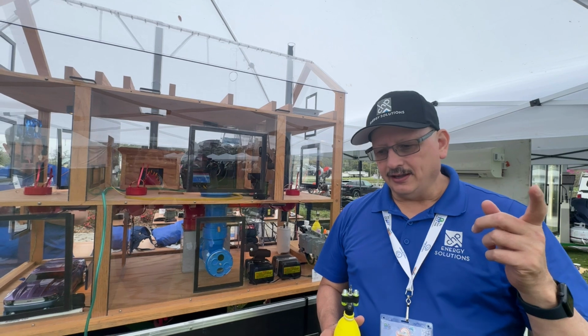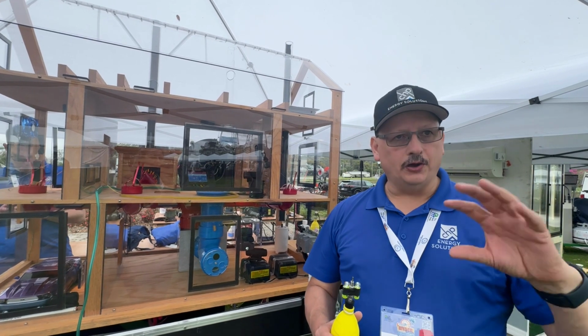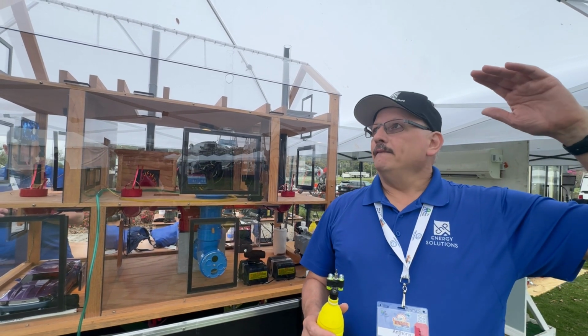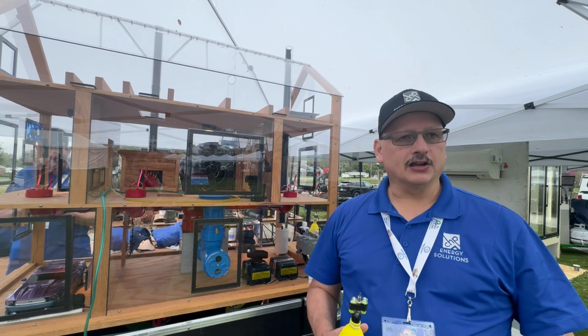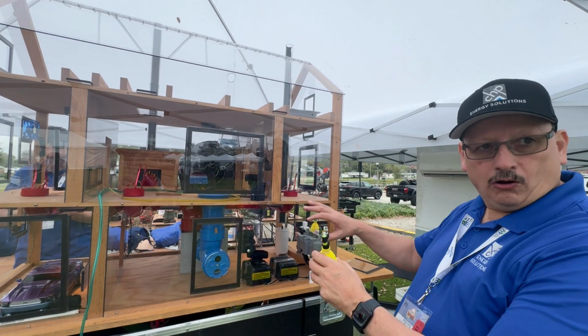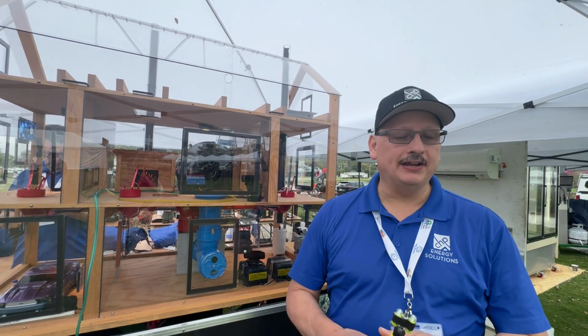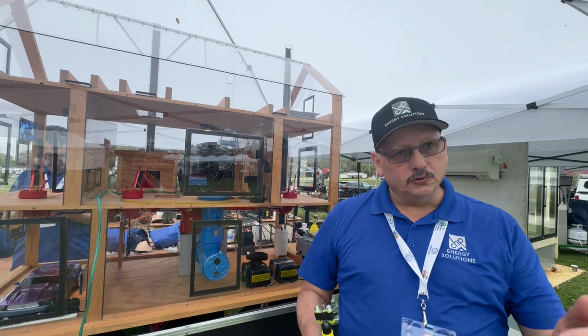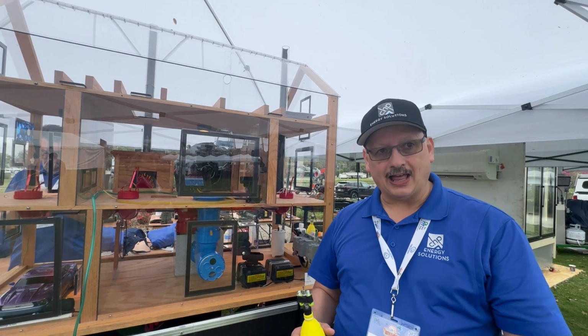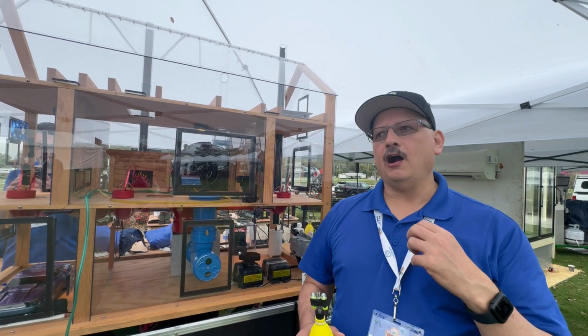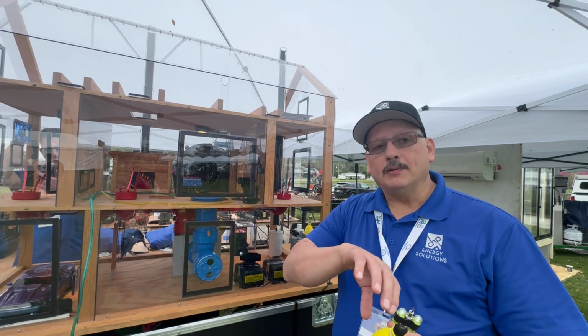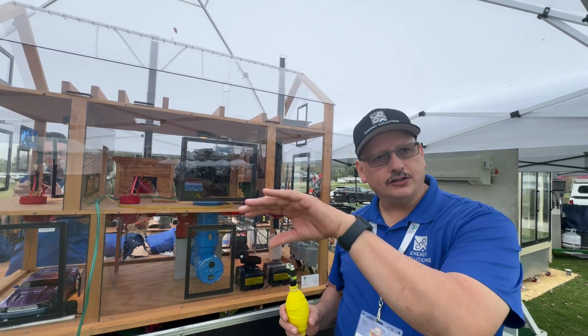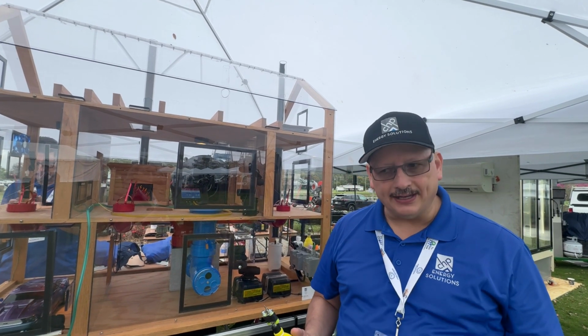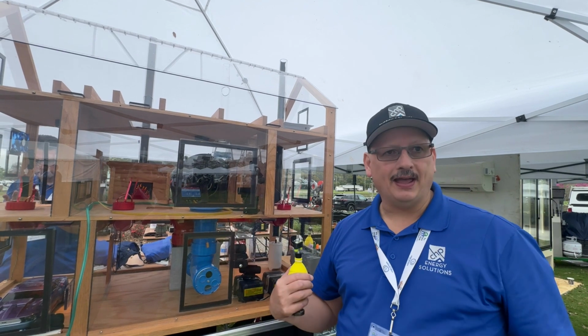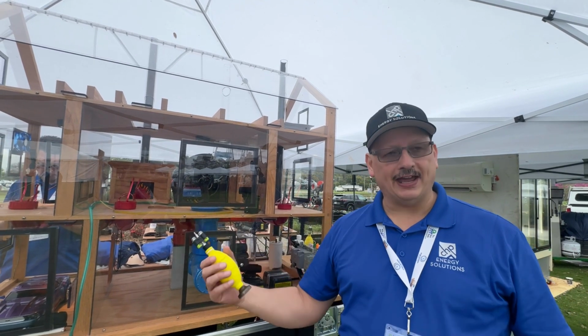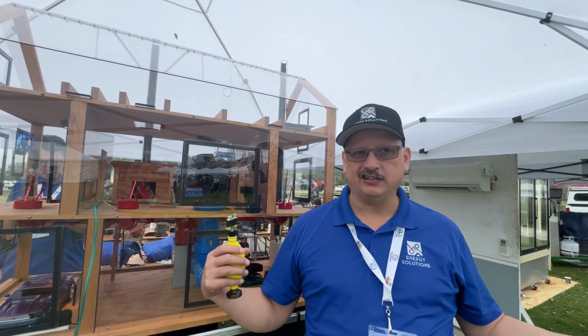Plus, it adds to what we call the load of the house. Your air conditioner has to work harder because you blew out your cold air and now you're replacing it with hot, humid air, which means you have to re-cool it. In a humid climate, that moisture is called the latent load. It's moisture being pulled into the house along with the heat, and now your system has to remove some of that humidity, or it's going to feel sticky and uncomfortable.